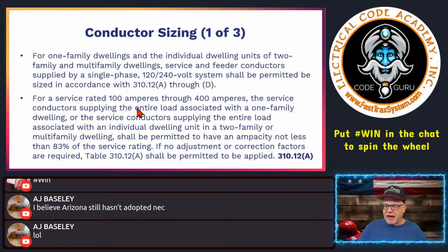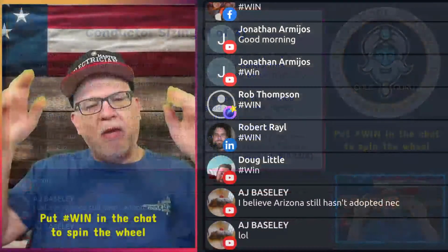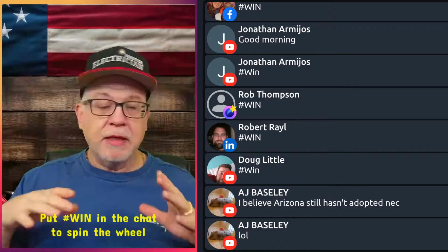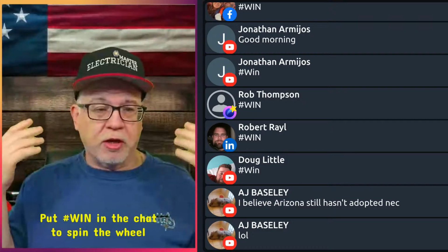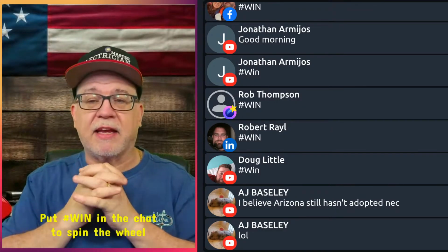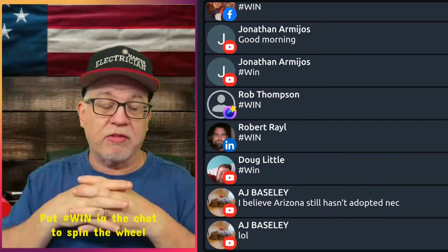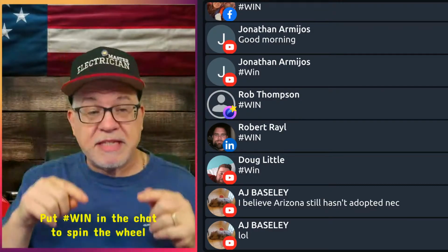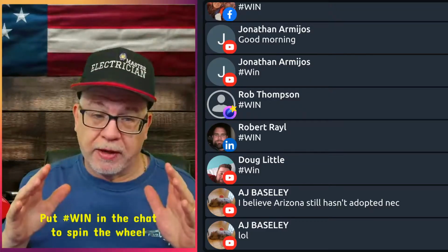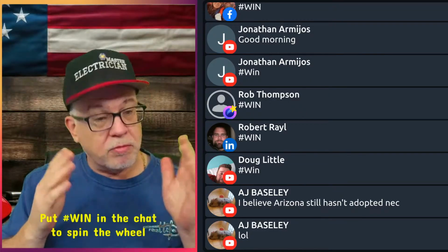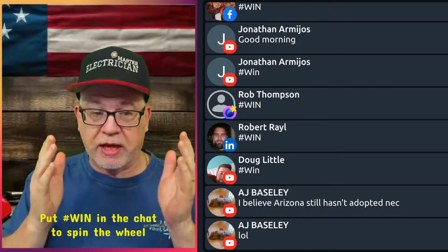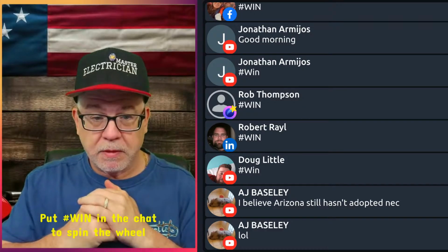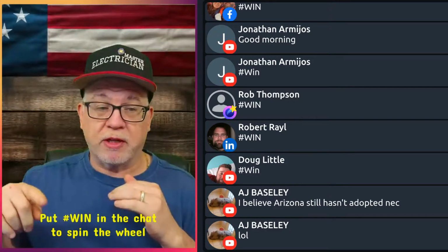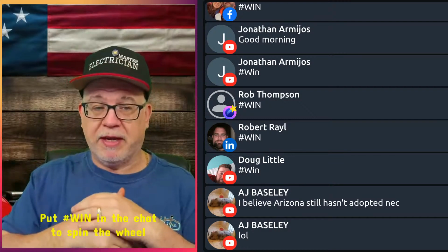But again, handling the entire load. So, I was going to give you an example. I have that weatherhead, I come down, I hit a meter, and then I hit a panel. All the loads are in that panel, you're good to go. All the way up to the weatherhead, it can't be less than 83% if you want to use this allowance. Now, what if I come down and I go through the meter and I hit an exterior panel, and it has a main breaker and is your service disconnect, and then at the bottom it has feed-through conductors and they're going into an interior panel.